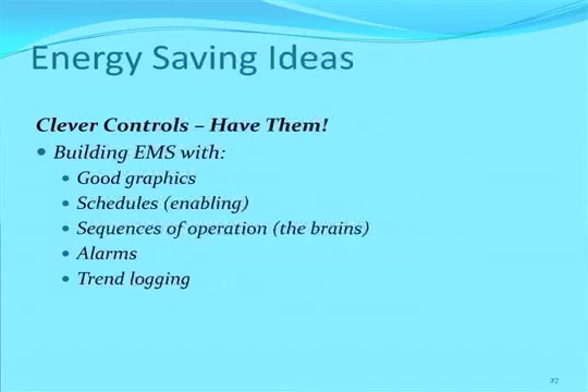Have controls, and I know that sounds moronic almost, but there are still buildings out there that operate by local mercury thermostats and breakers to turn equipment on and off. That's fine, it works, but it's not great. And these buildings that are operating that way are operating essentially in the blind. They don't have diagnostics as far as when they're bleeding their energy away and when they're operating inefficiently. They don't have signals that go on when something's failed or on the verge of failing.